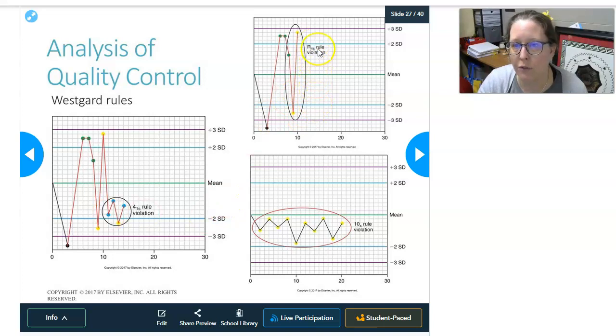Then there's an R4s. This definitely indicates a lack of precision, and this is when the difference between 2 consecutive points is more than 4 standard deviations. So this one goes from being out below 2SD to out above 2SD. This is not good. This is too big of a jump, and if you have a lot of them, it could be an indication of a problem with precision on your analyzer.